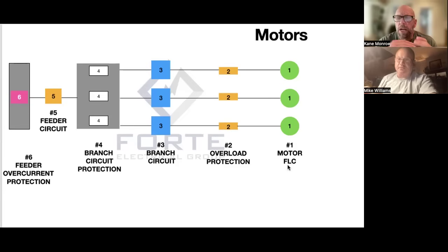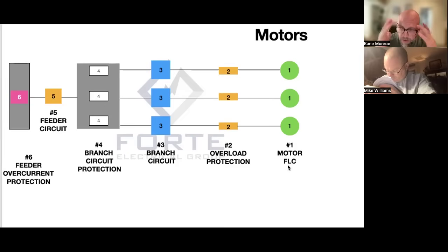And what we're trying to do here is make up a little bit of time so you're not having to remember all this stuff. It just comes to you. It's right there. So step 1 is 430.250. It's the tables back there. Yeah, and step 2 was 430.32. Yes, correct. So okay, I got that noted on the flow chart.